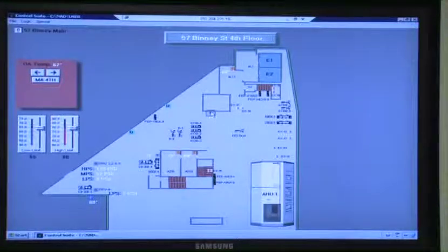Well, okay. One thing we might have to put in is another hyperlink for a mechanical room ventilation graphic to show how this is all being ventilated, because I can't tell from here. I don't think we have any that actually tell us how this is being ventilated. We have fan coils, we've got an H&V that serves this? You don't have an H&V that serves this. We don't have any H&V? No, you just got the exhaust fan, and the fan coils, exhaust, and unit heaters. That's what you got for that.